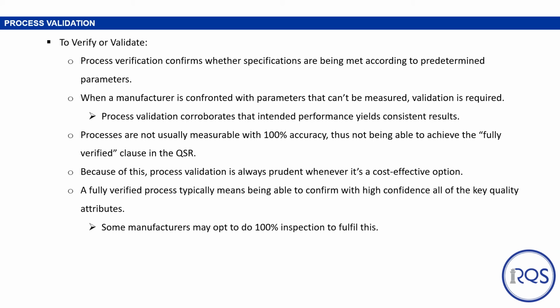So to verify or validate is sometimes a question. Process verification confirms whether specifications are being met according to predetermined parameters. When a manufacturer is confronted with parameters that can't be measured, validation is then required. Process validation corroborates that intended performance yields consistent results. Processes are not usually measurable with 100% accuracy, thus achieving the fully verified clause is not always possible. Because of this, we typically need to have process validation, and process validation is sometimes the more cost-effective option.